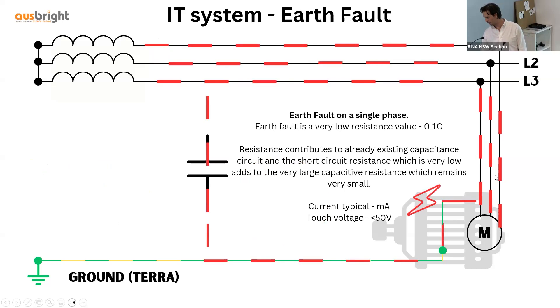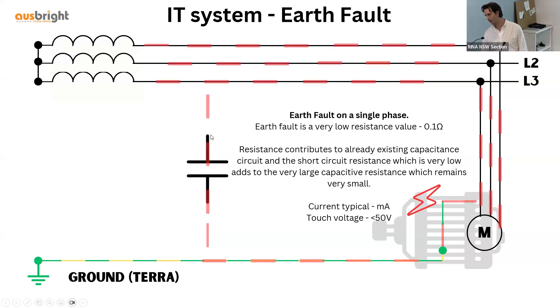We've now had an Earth fault between line three and Earth, shown here. Because you have a very large impedance value from the capacitive insulation resistance, this adds to the fault path, and you'll have a very small current flowing. The low impedance path remains through the plant, and the plant will continue to operate as normal. That is the main advantage of an IT earthing system — if you have an Earth fault, the system will continue to function.